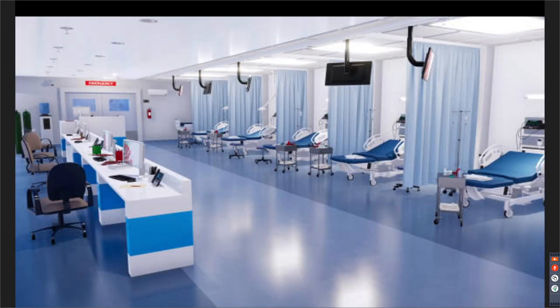So what do we know about what we've talked about so far? If this is a recovery area or pre-op in a clinic, is a single door down at the end of the room sufficient? Maybe yes, maybe no. Obviously, we don't have enough information, because one of the things we need to know is, what is the area of this room? If it's more than 2,500 square feet, then 2 exits are required. But it's not a sleeping room, so the 50-foot travel distance doesn't apply. But what about the maximum travel distance to the corridor of 100 feet? So all of these things need to be taken into account and drive the requirement for access to 2 exits.